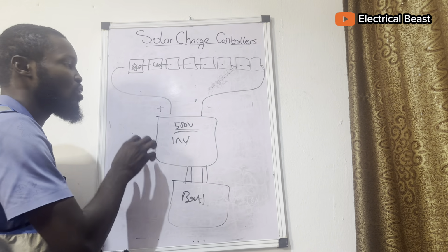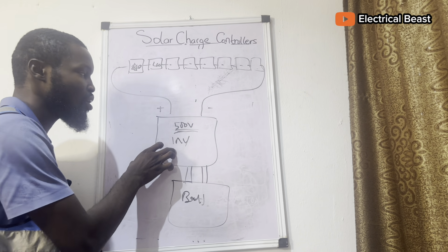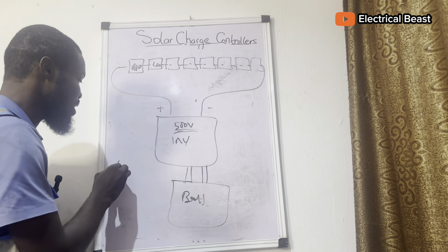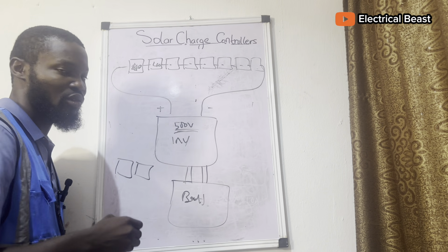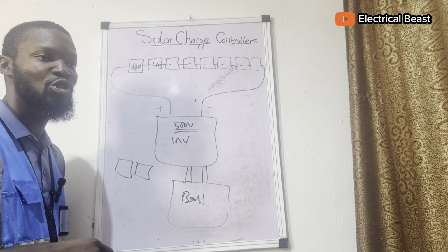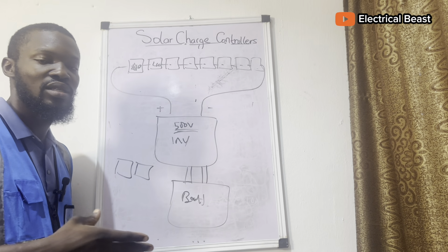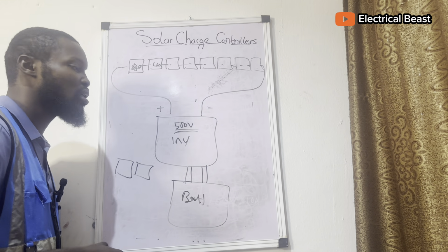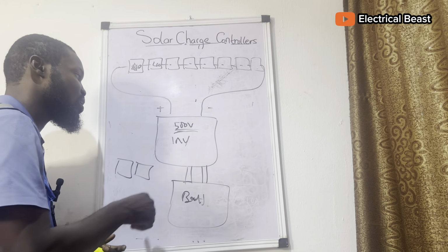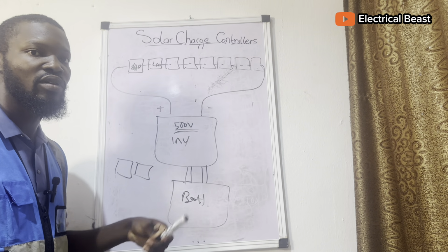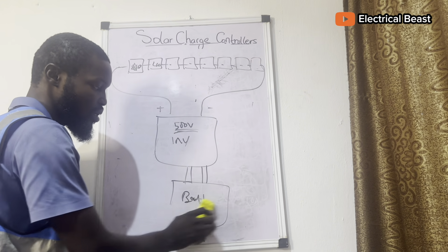Don't connect your hybrid inverter to a controller in an already existing system that had a controller that did 3 series, 4 series, because when you do that, the high current is going to destroy the controller inside the inverter. So that is that for that.